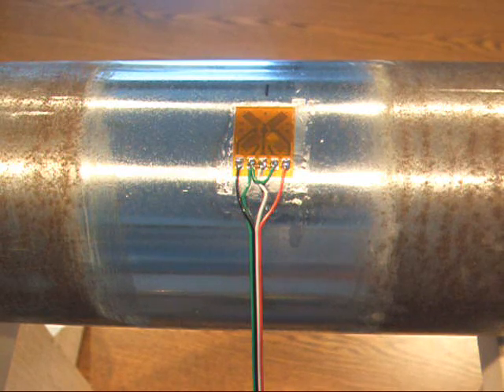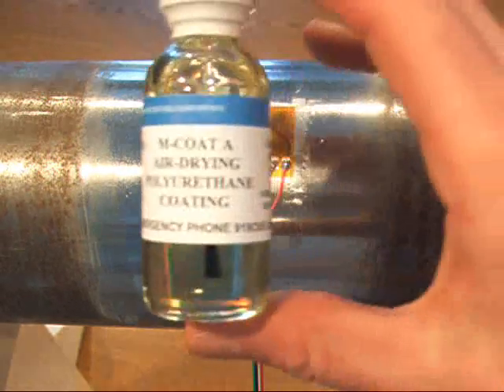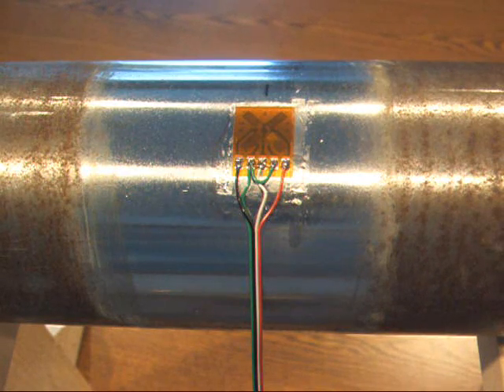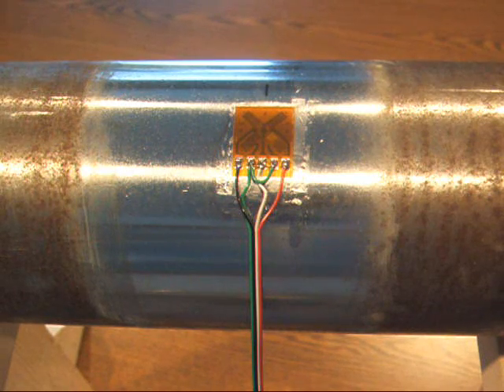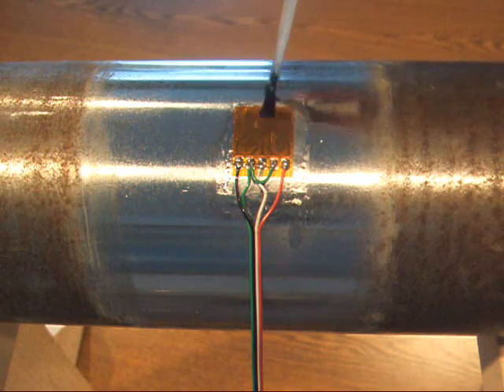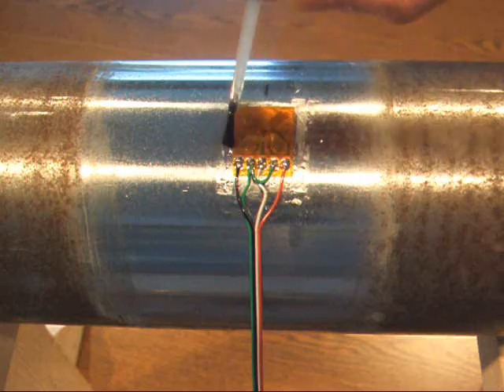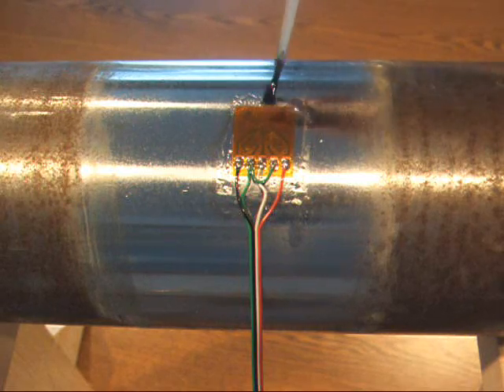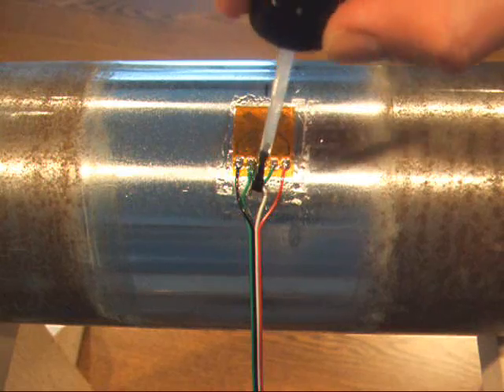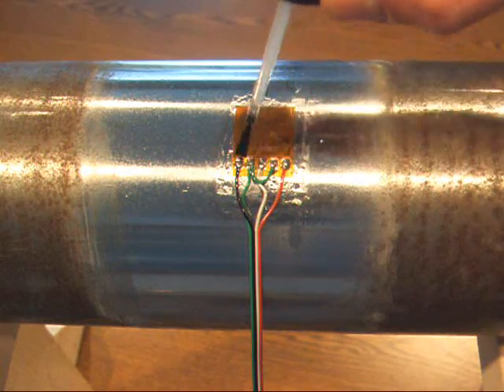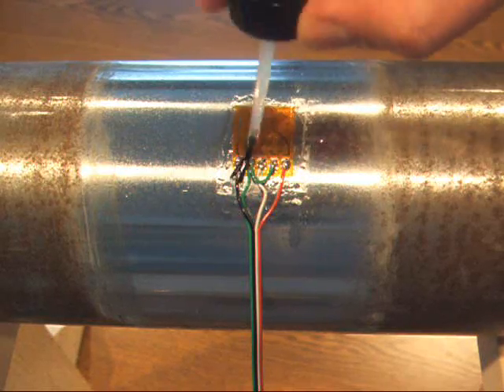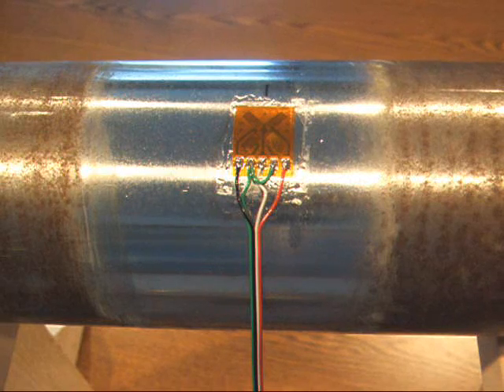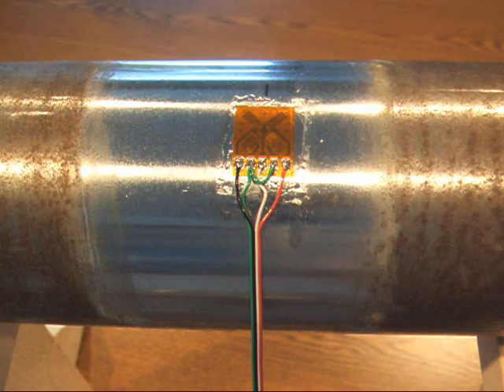After the rosin solvent dries, next you apply the air dry polyurethane. Completely coat the entire gauge with the urethane, as well as the lead wire and solder connections. This waterproofs the gauge and provides a very minimal amount of protection as well. Just brush it on. Make sure you get in between all the conductors. And allow that to air dry for several minutes.